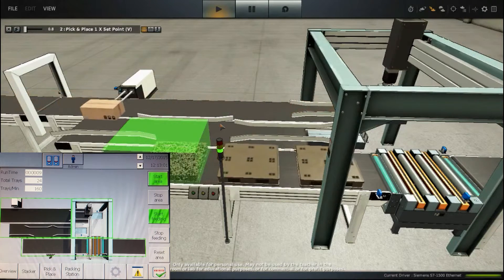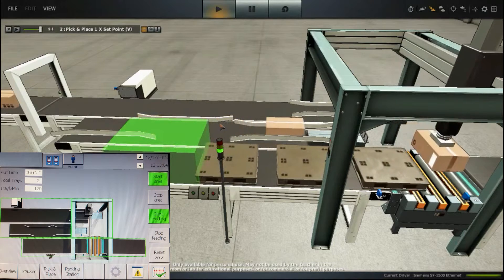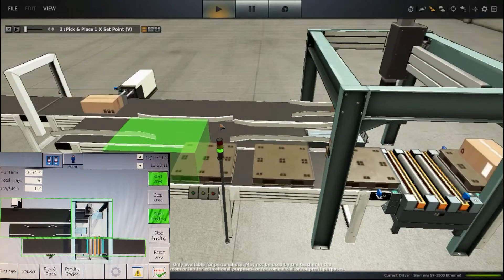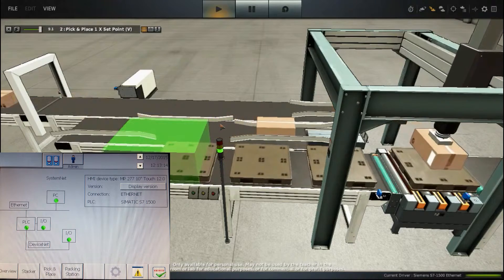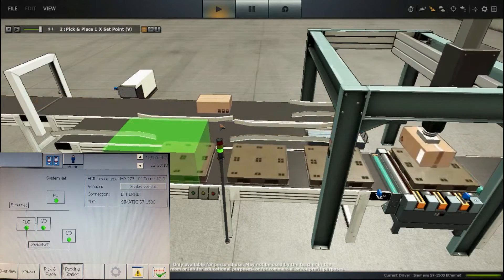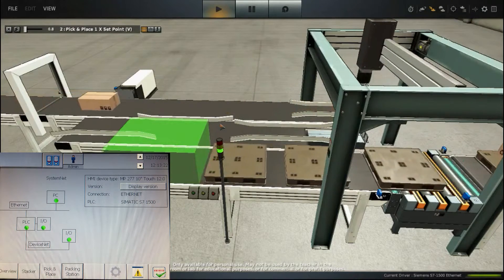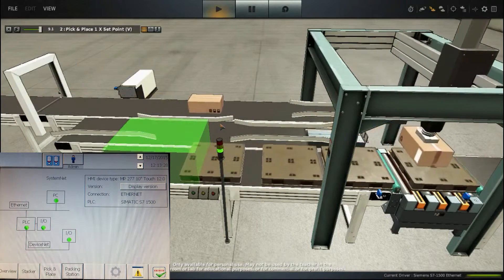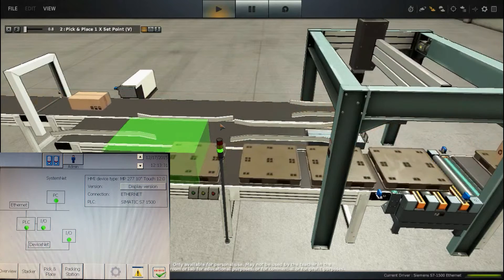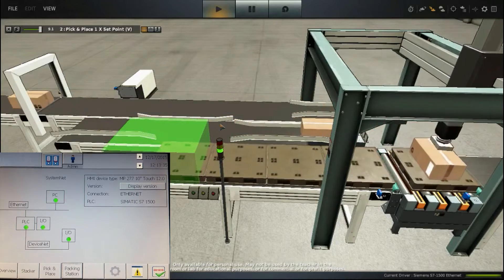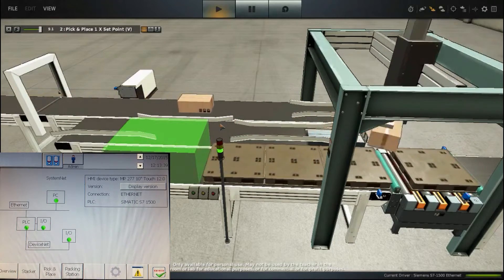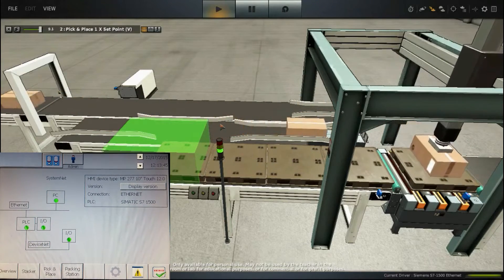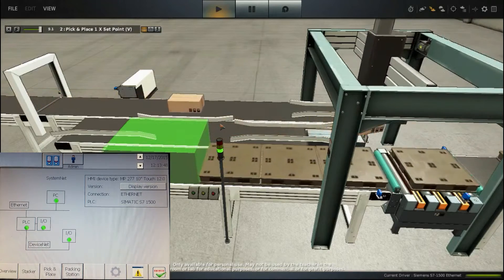I mentioned in the beginning that the pick and place is designed using the Graph language, and so are the three various modes the system can be in: auto mode, the screen mode that we are in right now, error mode, and in between there is a standby mode. I've used SCL for the alarm functions, which looks up in a data block and finds all active errors, then sets the system into error mode if there is any. Most of the other components are programmed in Ladder. I used Ladder, SCL, and Graph primarily.